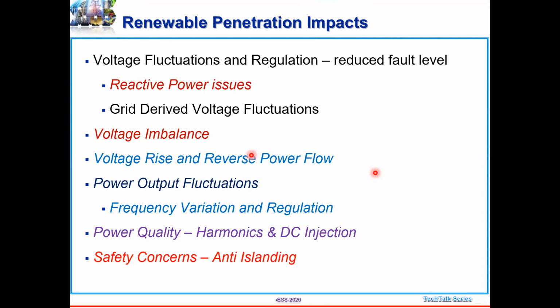In safety concerns, anti-islanding features are also there. Now we really have a concern on this, because in our normal load on the distribution system, in the LT system, at least in urban areas, the loading of the LT lines will be very, very low during the day. Only fridges will be there, because most people will be going to office or school. So the loading will be very low. At that time, if you have multiple solars coming in the same grid, and if the islanding protection is not proper, then you can have anti-islanding concerns.